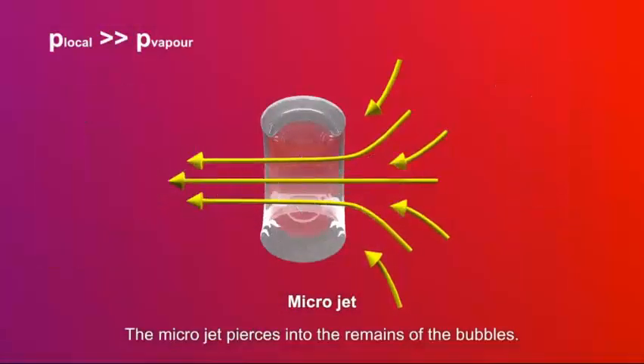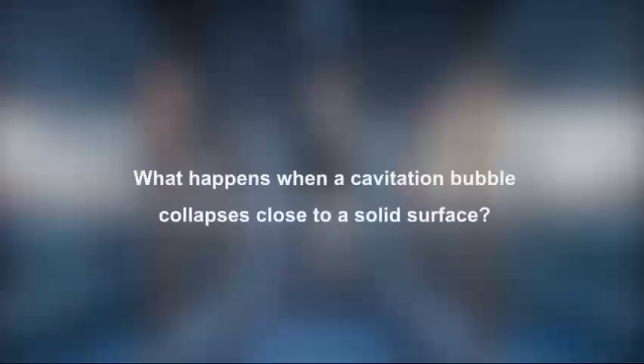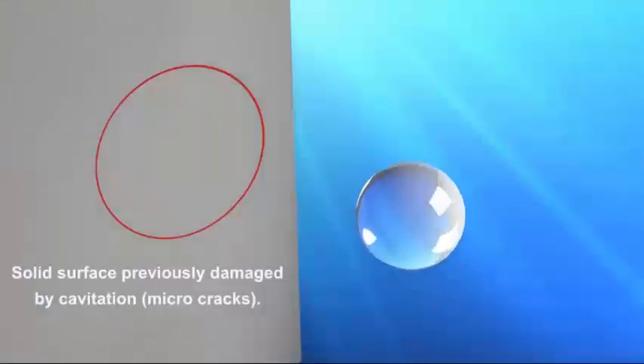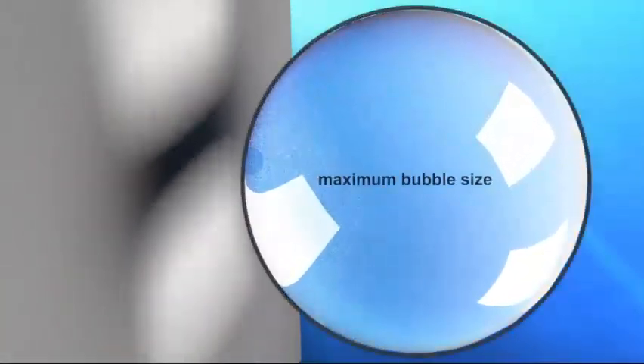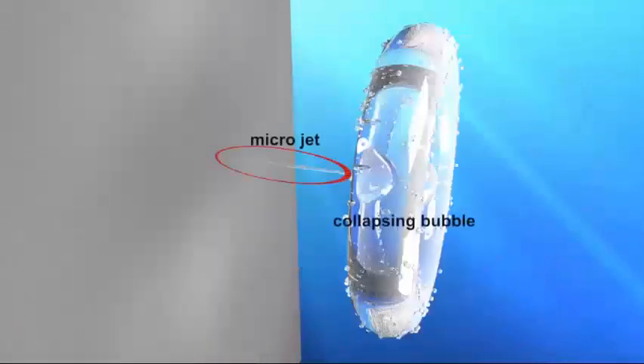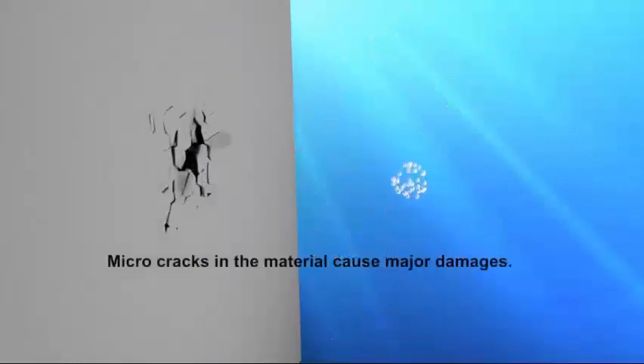The bubble becomes a torus and disintegrates further. The microjet continues to flow in the liquid and can hit a wall. Through its concentrated impact, even high-strength material can be damaged. The implosion releases energy in a very short time concentrated in a very small spot. If the microjet hits a surface, it damages the material by a localized short-term overstraining. The material starts to develop microcracks, and later, material can break off.